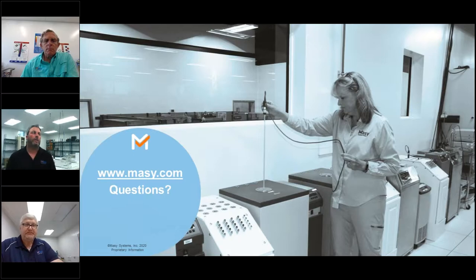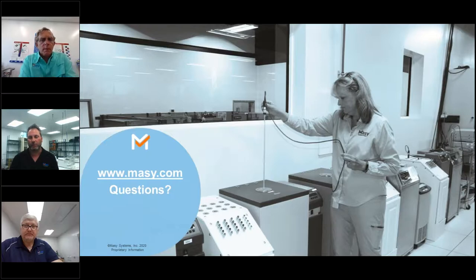Another good question. Based on the earlier presentation about process equipment versus working standards, personally, anything that is a standard is a must, because it's a higher level of calibration. It's easier to do deviations, especially for the end user. If you have an excursion or out-of-tolerance condition on your standard, it holds a little more water because you're taking everything into account in the measurement.